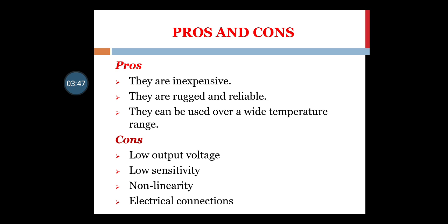These are the pros and cons of the thermocouple. The pros: they are inexpensive, rugged and reliable, which is a good thing, and they can be used over a wide temperature range. And the cons: low output voltage, low sensitivity, non-linearity, and electrical connections.